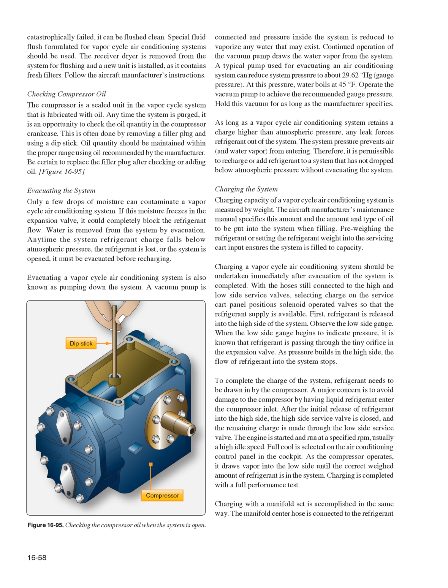Charging the system. Charging capacity of a vapor cycle air conditioning system is measured by weight. The aircraft manufacturer's maintenance manual specifies this amount and the amount and type of oil to be put into the system when filling. Pre-weighing the refrigerant or setting the refrigerant weight into the servicing cart input ensures the system is filled to capacity. Charging a vapor cycle air conditioning system should be undertaken immediately after evacuation of the system is completed. With the hoses still connected to the high and low side service valves, selecting charge on the service cart panel positions solenoid-operated valves so that the refrigerant supply is available.